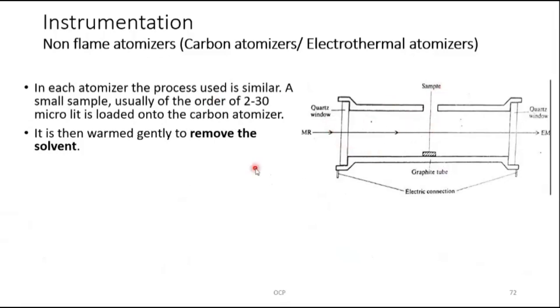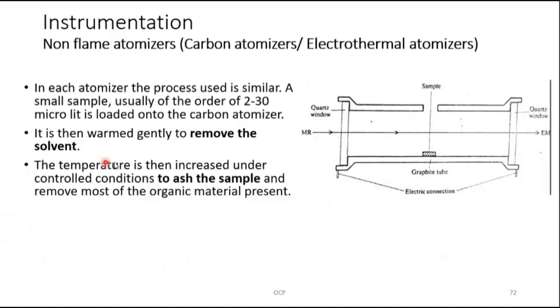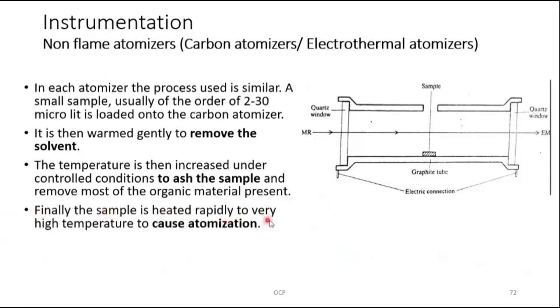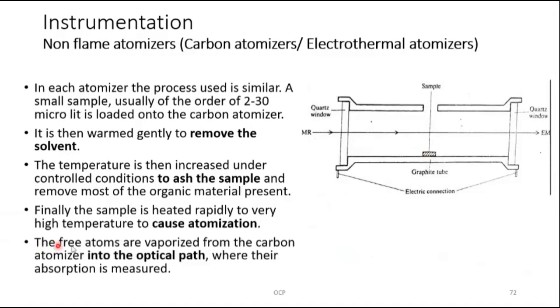The process: first, the sample is introduced. Second, it is warmed gently to remove the solvent, leaving behind the residue. Third, the temperature is increased under controlled conditions to ash the sample — converting it to ash and removing most organic material (carbon, hydrogen, oxygen). Finally, the sample is heated rapidly to very high temperature to cause atomization.